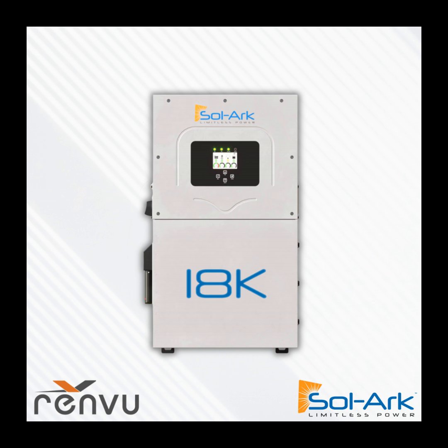It is stackable, so you can do very large systems. If you're doing agricultural or commercial application, you might be getting into some 2,000 amp agriculture on split phase, pretty intense stuff. You can do that with the Sol-Ark. I think for 400 amp service, there's no better platform than a Sol-Ark. You just use 2 inverters, not 1.